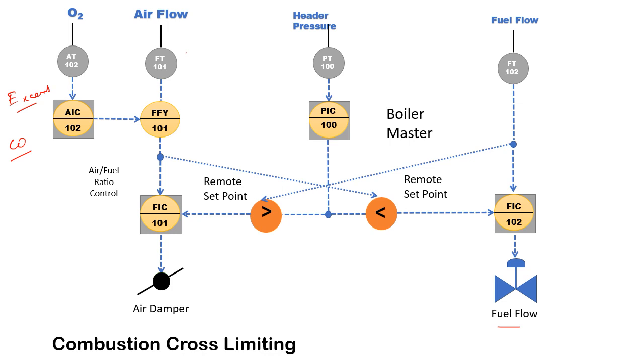Both the high selector and low selector are configured in the DCS to achieve cross-limiting. The high selector always allows more air into the furnace and the low selector always allows less fuel into the furnace, so there is no chance of accumulation of fuel.